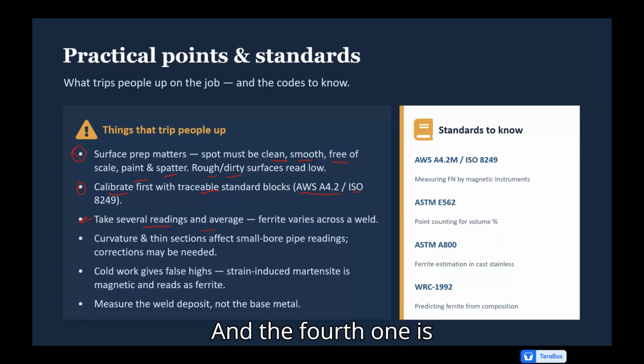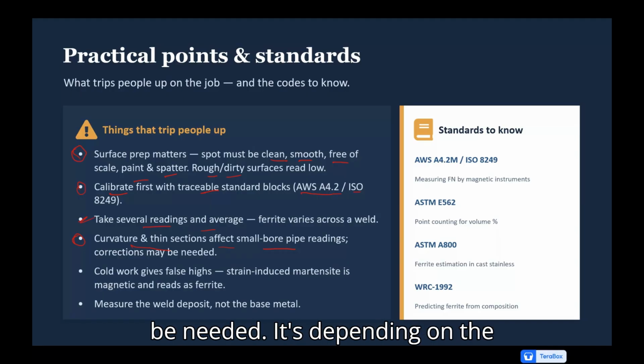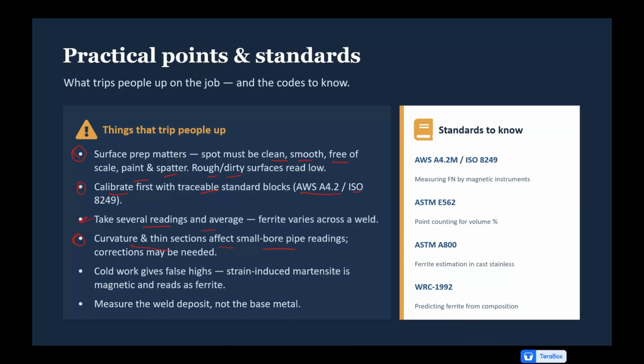Okay. And the fourth one is curvature and thin sections can affect the reading. So this is very important for small bore pipe. If the pipe diameter is small or the section is thin, the magnetic field response may be affected. In that case, correction factors or special calibration blocks may be needed. It depends on the instrument and procedure.